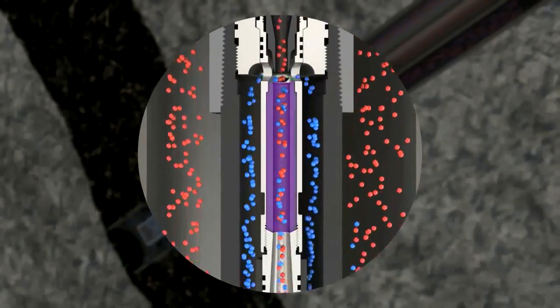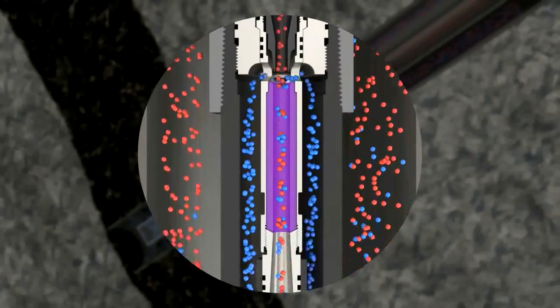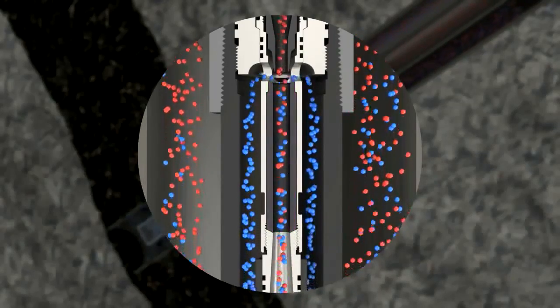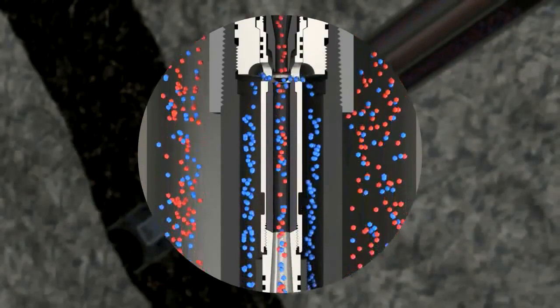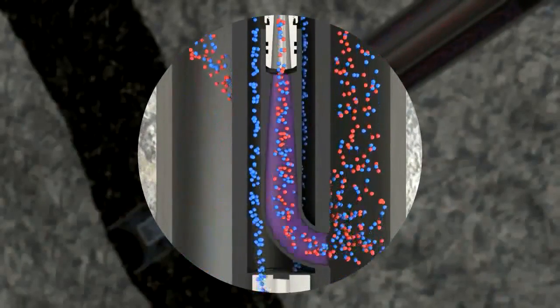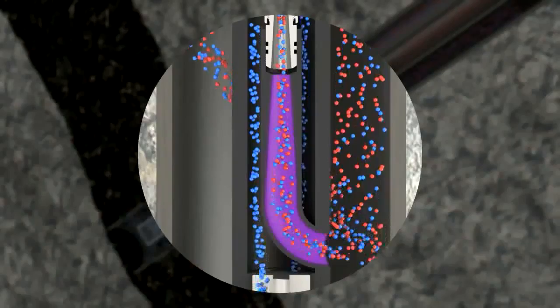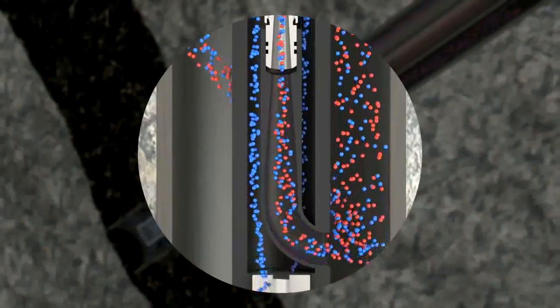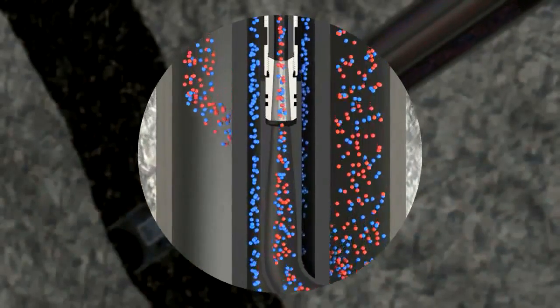In a mixing tube or throat, the power fluid encounters the produced fluid, where it combines and accelerates to an average velocity. In the pump's diffuser, the velocity of the mixed stream is converted back to pressure and the combined fluids lift to the surface.